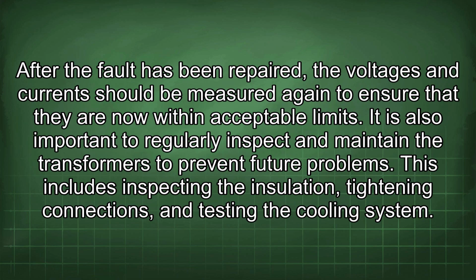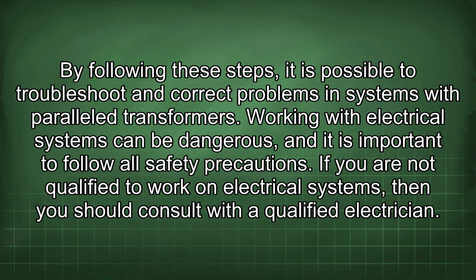After the fault has been repaired, the voltages and currents should be measured again to ensure that they are now within acceptable limits. It is also important to regularly inspect and maintain the transformers to prevent future problems. This includes inspecting the insulation, tightening connections, and testing the cooling system. By following these steps, it is possible to troubleshoot and correct problems in systems with parallel transformers.